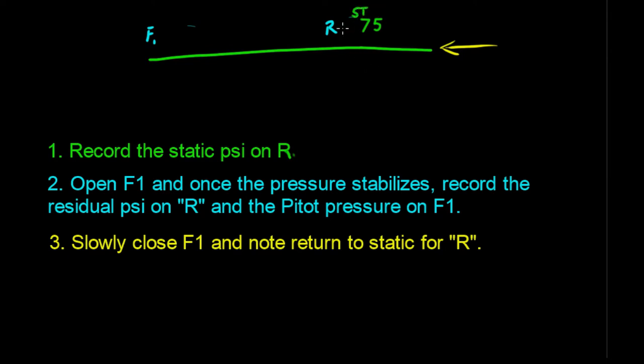And then we'll go ahead and hook our test equipment up to it while this person is reading that. It's best to have two people and be able to have hand signals or radios to communicate. If you can't see one another, you've got to communicate. Because the next step is once you've taken this reading, you give the signal to this person here, and they'll open this hydrant up all the way, and you need to flow it for 60 seconds or until the water runs clear. Now, if you're using a hose monster or something, be sure and have the pitot pointed away in there. If you have a hose monster, you'll know what I'm talking about.